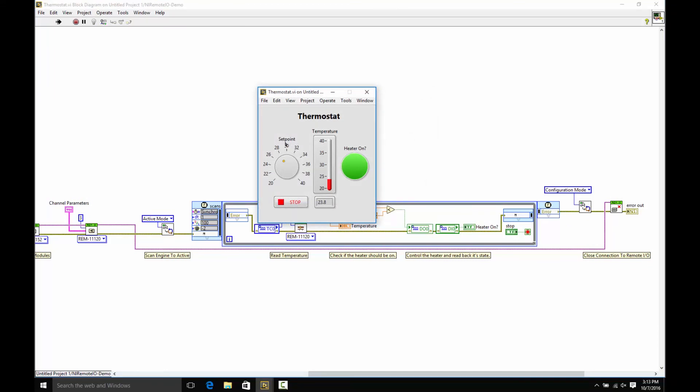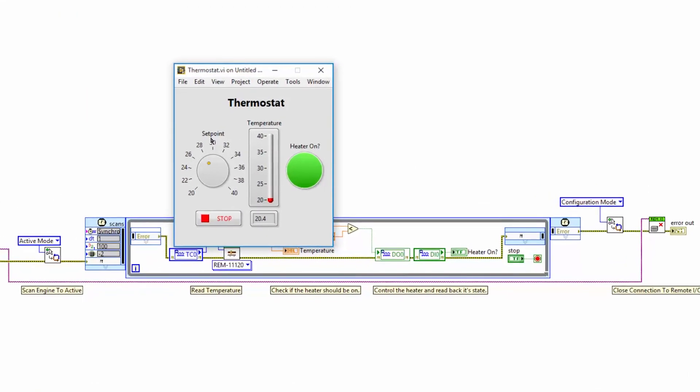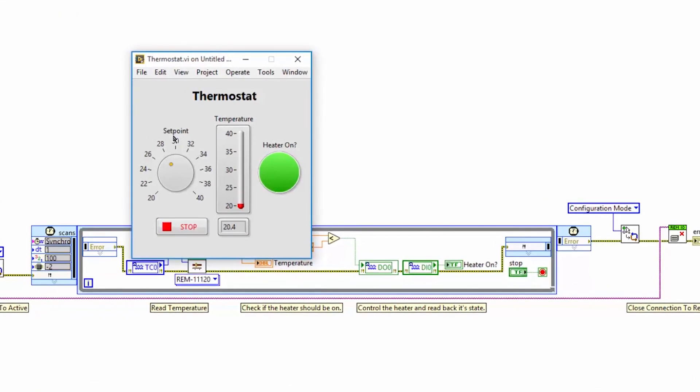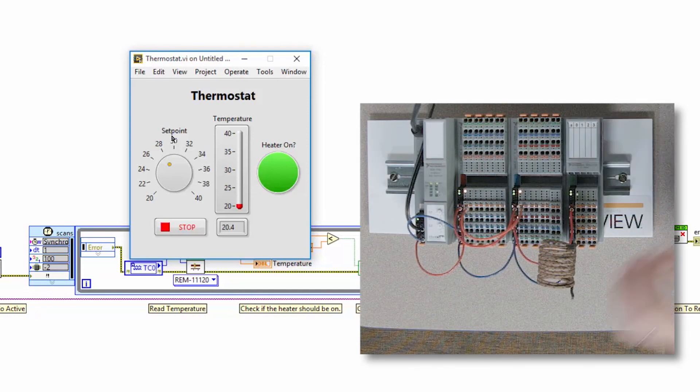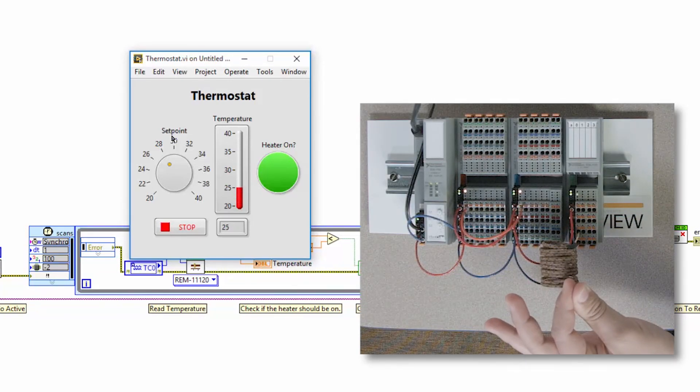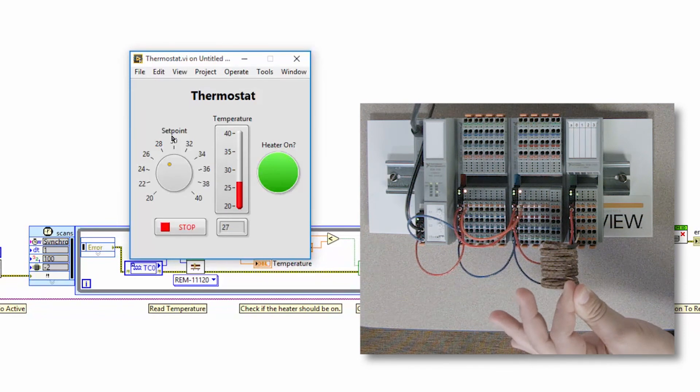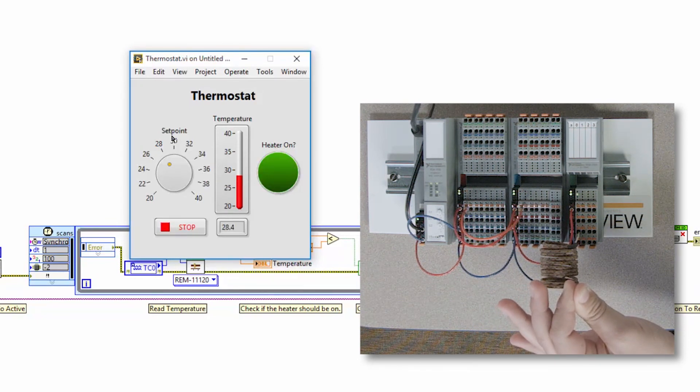It automatically deploys, and what you can see is the current temperature of the thermocouple and our setpoint, which is currently around 28 degrees Celsius. Because setpoint is above the temperature, our heater is on, but if I just hold the thermocouple and get it above 28 degrees, our heater should automatically turn off. There we go.